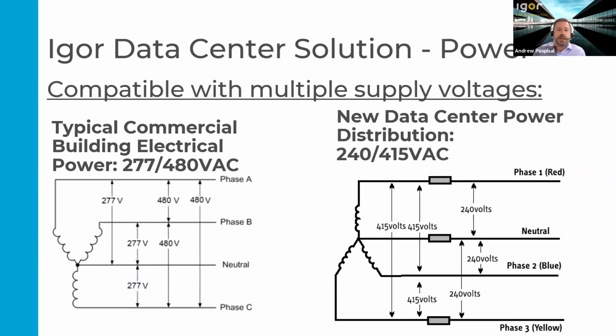Typical commercial building, traditional data center in the past has incorporated your typical 277, 480 volt, 3-phase power distribution in the building, and so while that's great for some of the higher power applications, it can have the requirement for more step down transformers in order to power all of the IT equipment within the building. And so anytime you have any transformers or other equipment, you're having efficiency loss through that voltage drop through that transformer.